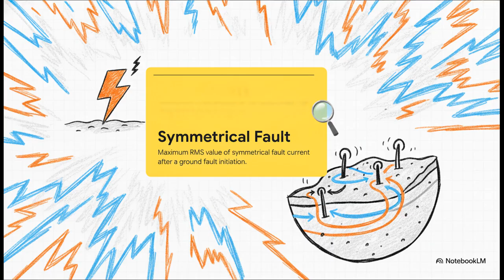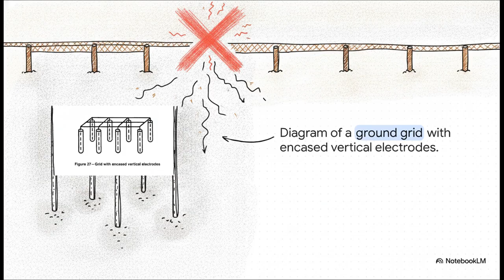Long before they ever pour a single ounce of concrete or install those giant transformers, engineers bury an intricate web of horizontal copper meshes and drive deep vertical electrodes straight down into the soil. This entire ground grid is specifically designed to grab that massive fault current and forcefully disperse it deep into the earth before it can cause any havoc above ground.